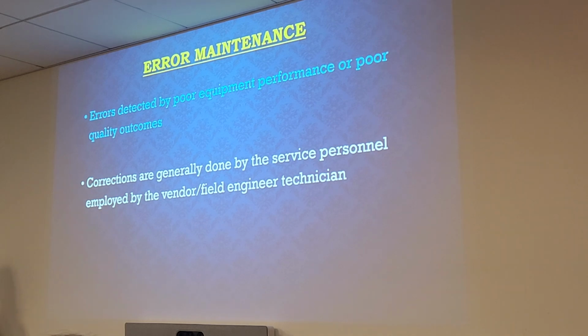Okay. So for error maintenance, errors are detected by poor equipment performance or poor quality outcomes. So again, if an artifact shows up on your image and you continue to use that cassette or that detector and you see that artifact constantly popping up, that's when you need to call, because there's an error maintenance issue somewhere. Call Biomed or you might even have to call vendor personnel.